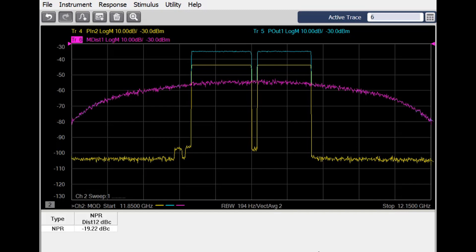You can see that this distortion trace lines up very well with the notch floor and also with ACPR levels outside the channel.